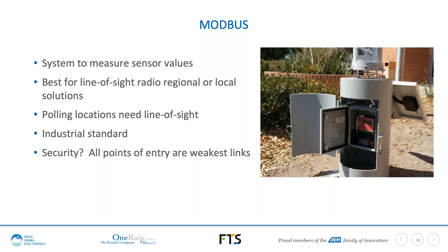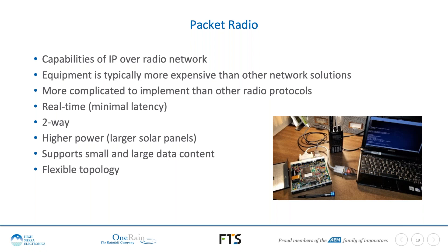Modbus requires line-of-sight radio, typically implemented with a hub-and-spoke architecture where the hub does the polling. The need for line of sight is one of the major issues with a radio-based system like this. From a radio protocol standpoint, Modbus is not very secure — any entry point is a weak link, and in a radio network, every site is essentially an entry point, as is the central polling master.